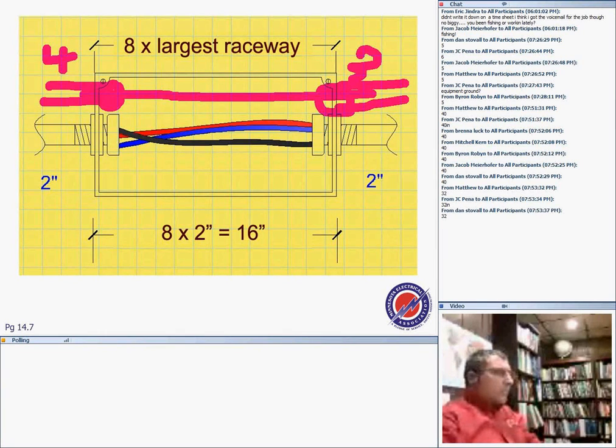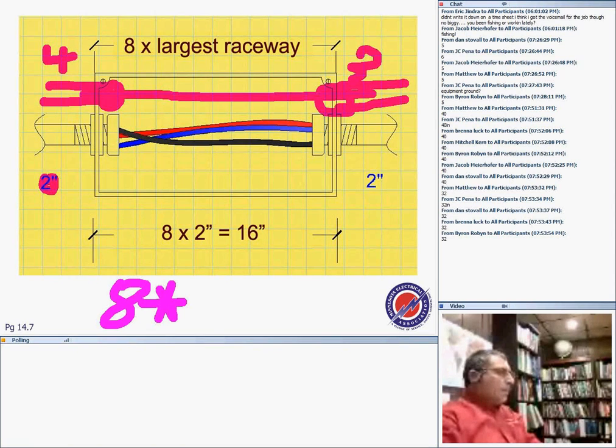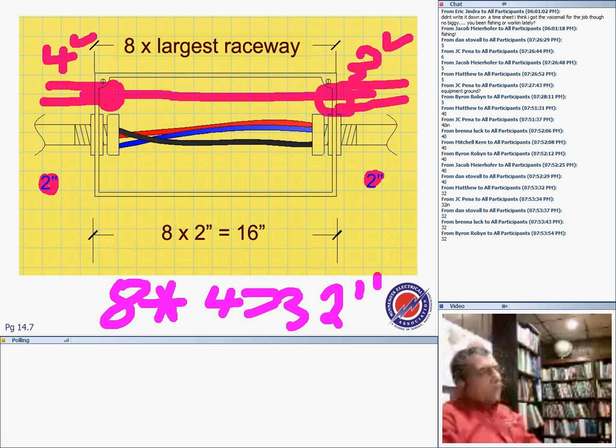All right. All participants here, you're supposed to send it to chat only, guys. All right. So you take 8 times the largest conduit engaged in the straight pull: a 2-incher, another 2-incher, a 3, and a 4. Which one is the largest? Obviously the 4. So 8 times 4, and if I did my math right, it's going to be 32 inches. 32 inches.